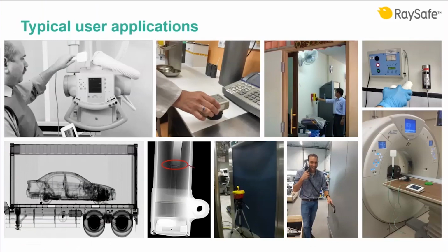Survey meters are being used wherever there are or could be radiation present, to control and minimize the unnecessary radiation to staff, patients, or to the public. It may be in hospitals for testing tube leakage or wall leakage, scattered radiation in the room, in nuclear medicine departments to check for contamination, or at radiotherapy departments.